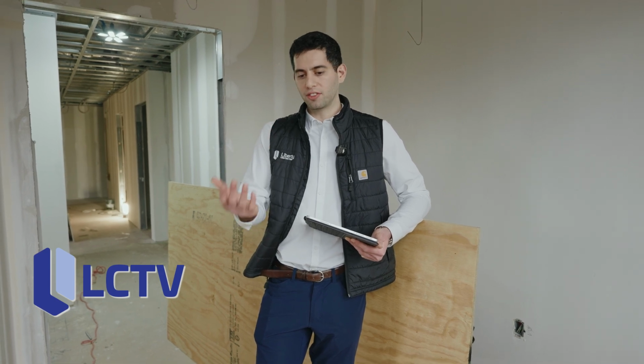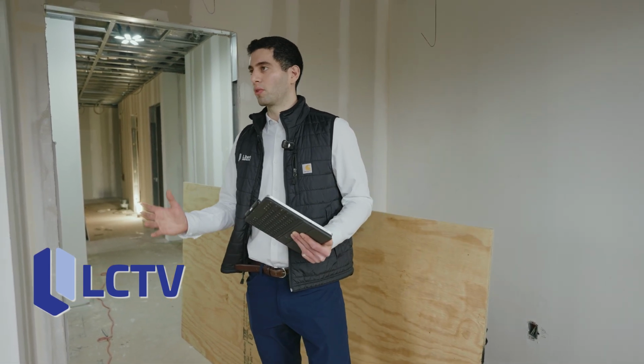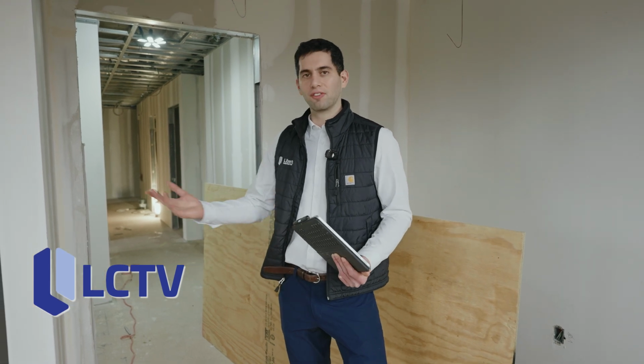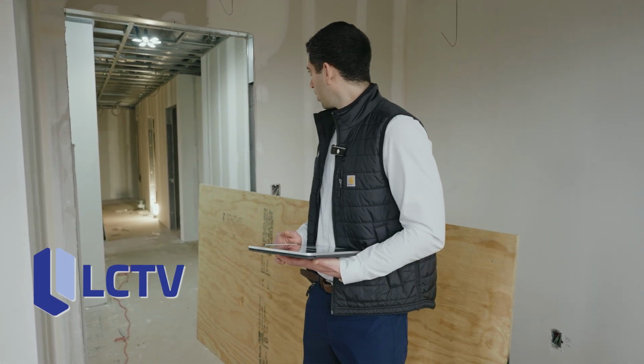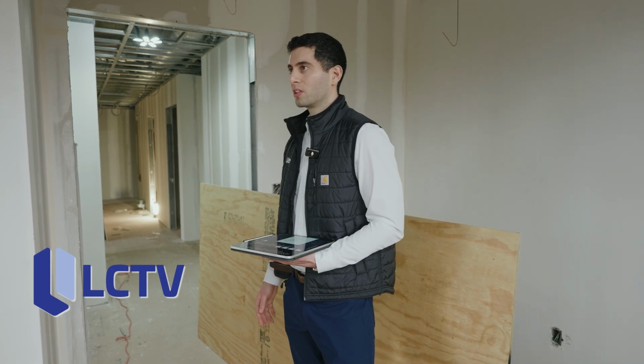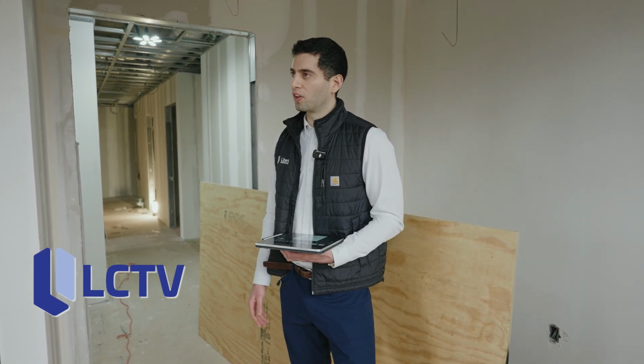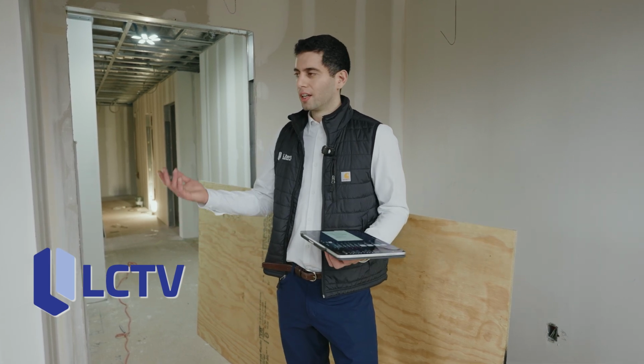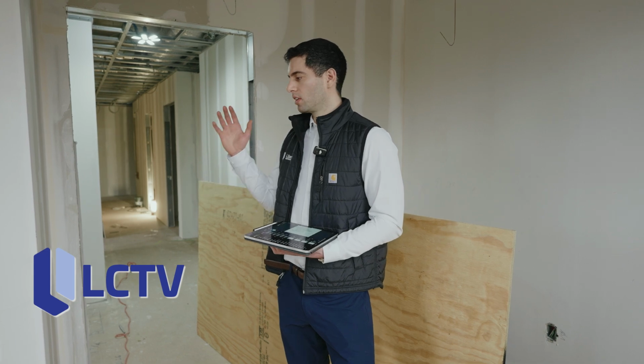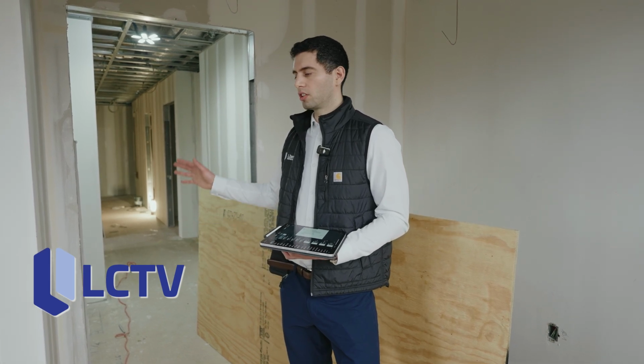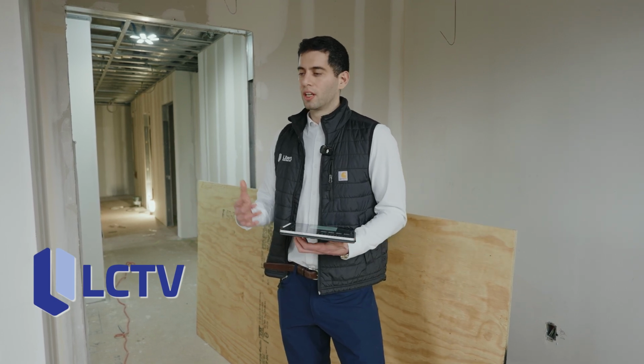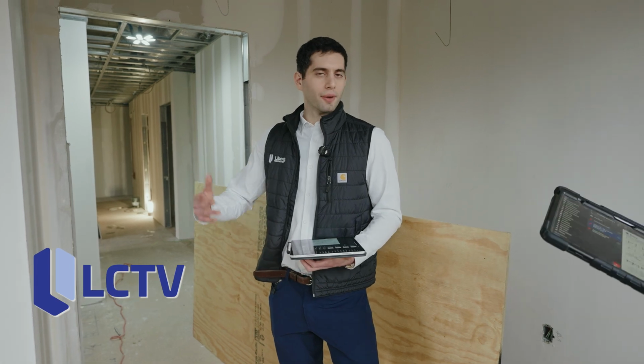Everything was balanced and good at the beginning, but you're gonna have a new layout, new CFM and air exchange rate requirements, and HVAC demand, especially when you partition a space more than what it originally was. You close doors, the airflow is hindered. We do by default a 1/2 inch undercut on all doors, which eliminates usually the need for a louver unless there's a very high temp piece of equipment like a compressor, which we don't have here. So typically for most medical offices, even just a 1/2 inch undercut on the door allows for enough airflow if most doors are closed, because usually for patient privacy doors are not usually open. That's been good enough, but that's why you want to do pre-balancing and final balancing.